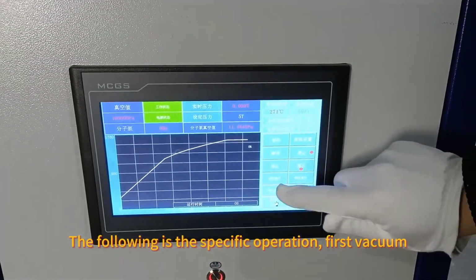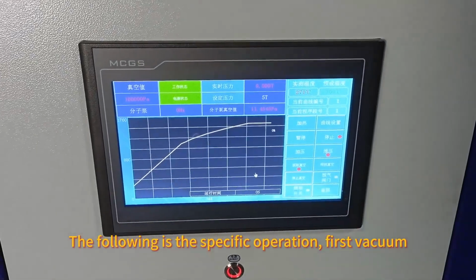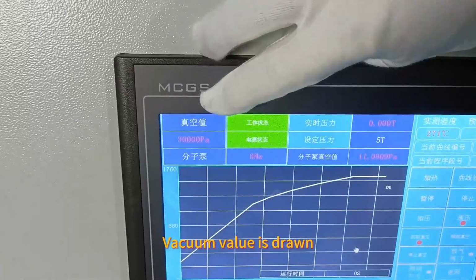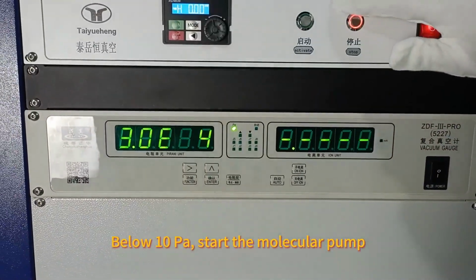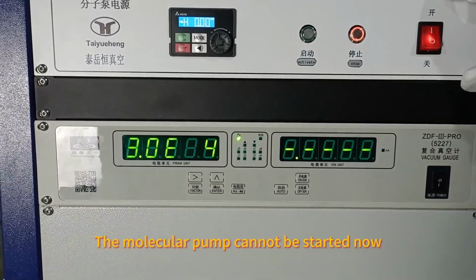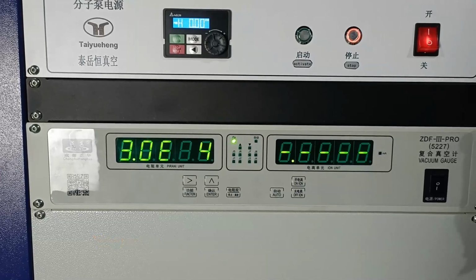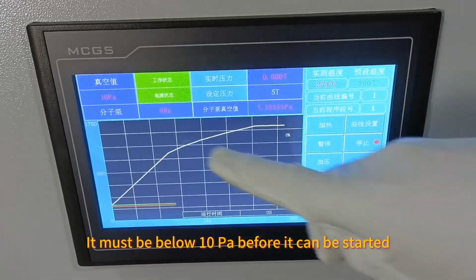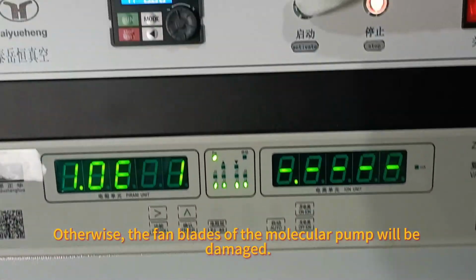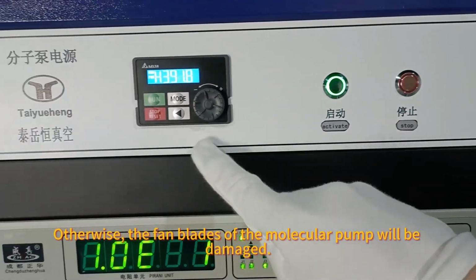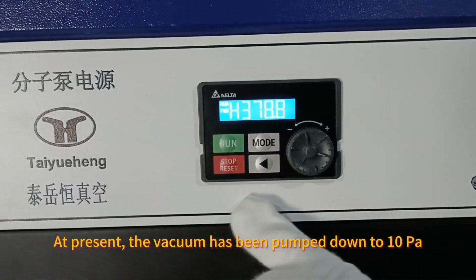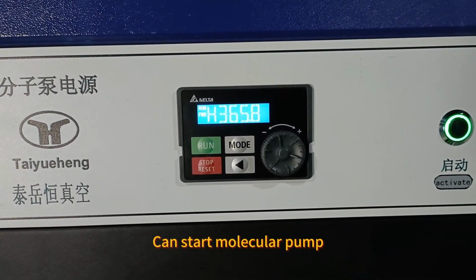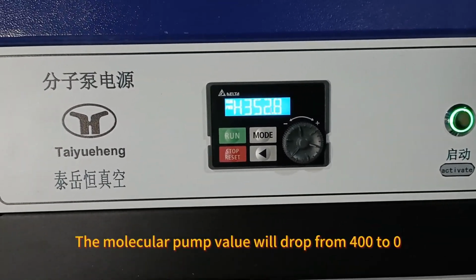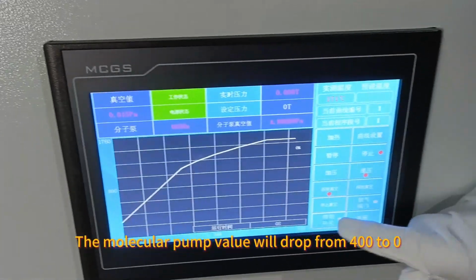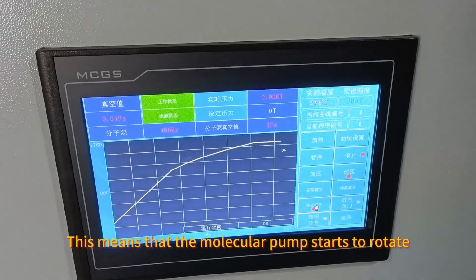The following is the specific operation. First, get vacuum. The vacuum value is drawn below 10 Pa. Start the molecular pump. The molecular pump cannot be started now. It must be below 10 Pa before it can be started. Otherwise, the fan blades of the molecular pump will be damaged. At present, the vacuum has been pumped down to 10 Pa. Can start the molecular pump. The molecular pump value will drop from 400 to 0, then it goes up from 0. This means that the molecular pump starts to rotate.